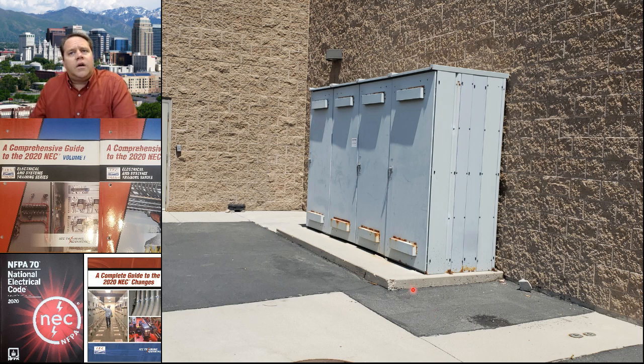So how would I solve this problem if this was a new installation? It's certainly a violation. How would I make it comply? Well, I would either have to cut it and make it not more than 6 inches, or extend it to the full working space, the full 3 feet in this application. Either way, that's how I would comply with this new rule.